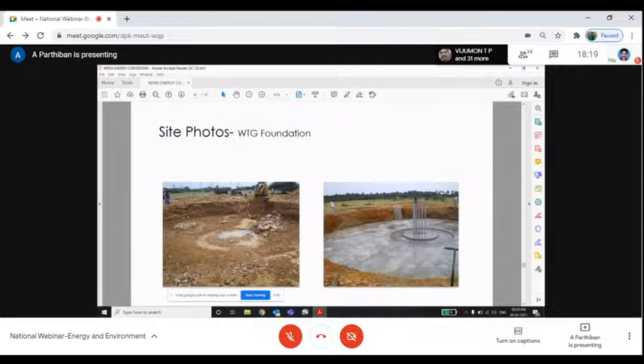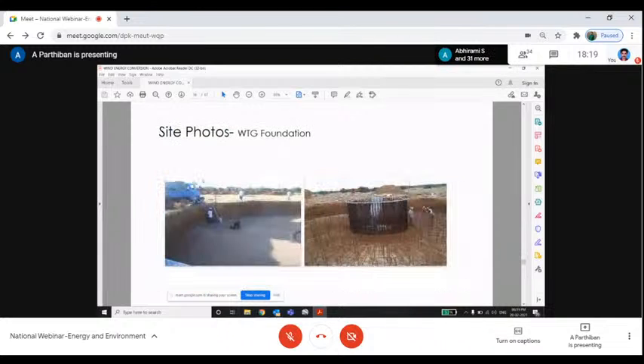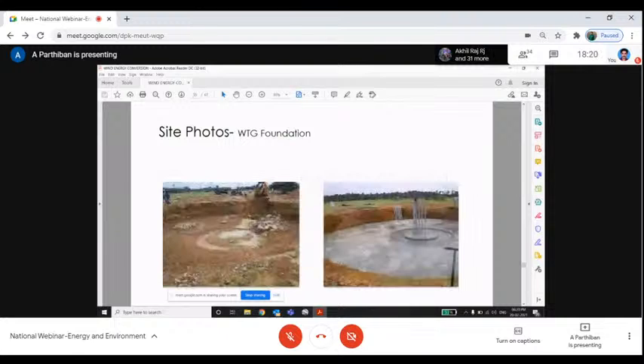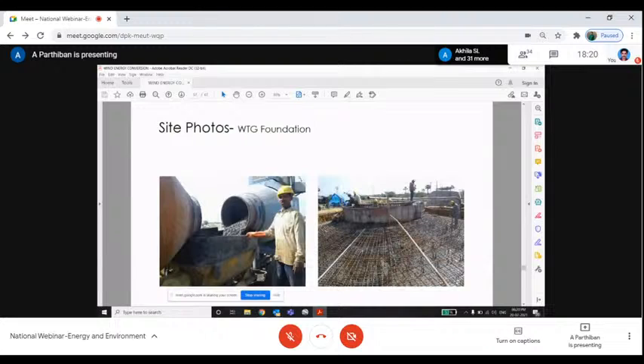because there should not be any rust, and the soil should not touch the steel portions. There will be a center portion, and there will be PVC pipes which will carry a cable, because the power cable will pass through these PVC pipes and it will be taken out. And these are all the anchor cage which hold the total tower setup, and these are all the steel reinforcement. For example, for a 2 megawatt tower, we need to use 35 metric ton of steel for this foundation. Once everything has been reinforced with steel, we will start the foundation activities.